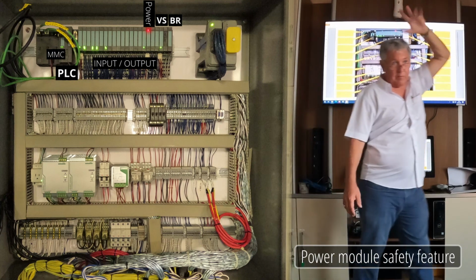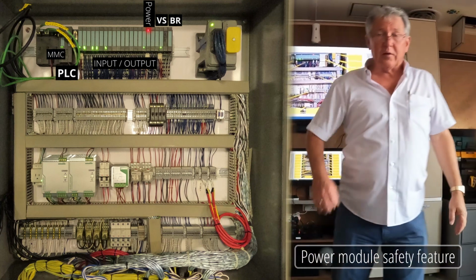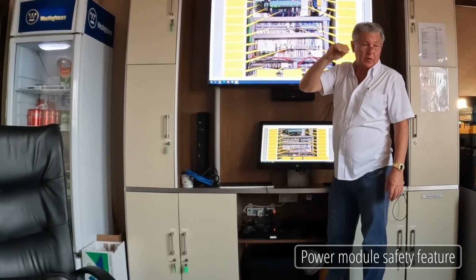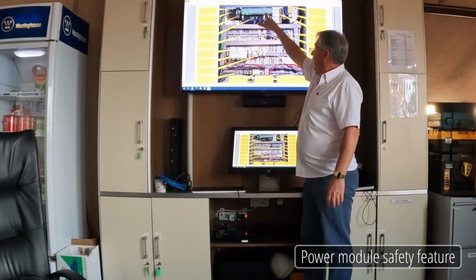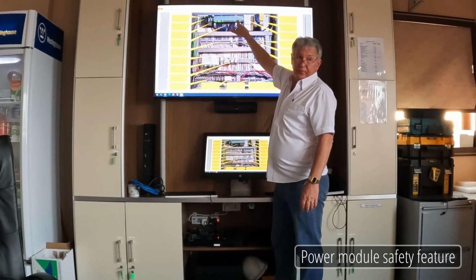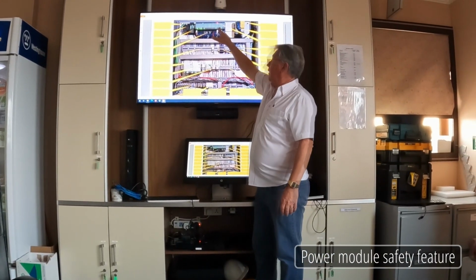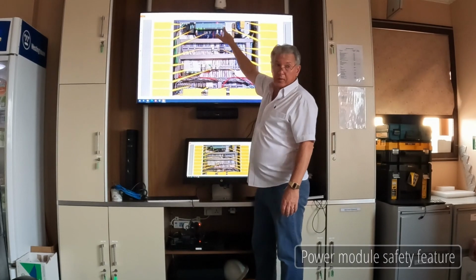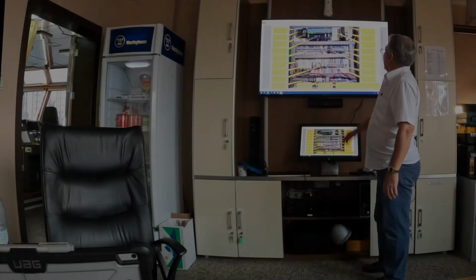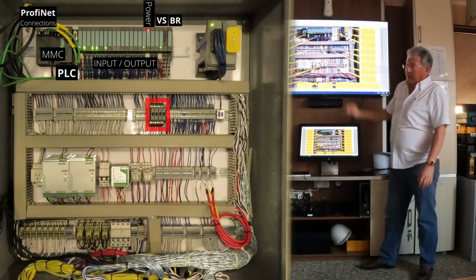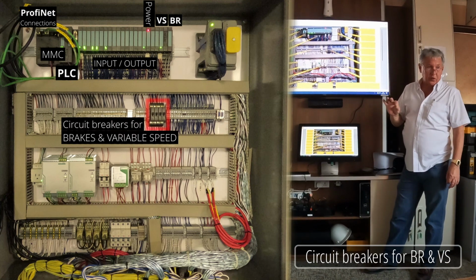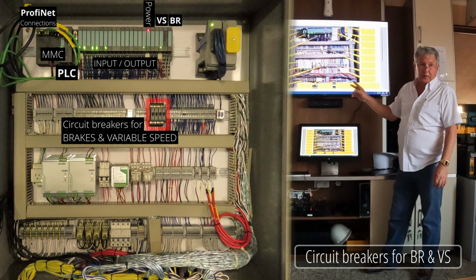Doesn't happen, but it can. So these 2 are for variable speed, these 2 are for brakes, and that power line is modulatable, so we can make sure the brakes never come on. The others are switches controlled by the PLC. When they're on, the brake solenoids fire; when they're off, the brake solenoids will not fire. 2 on HPU A, 2 on HPU B. This box here has the individual circuit breakers for the brake solenoid and the variable speed solenoid, first 2 are brake, second 2 are variable speed.